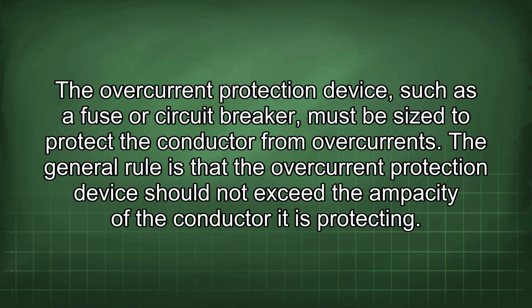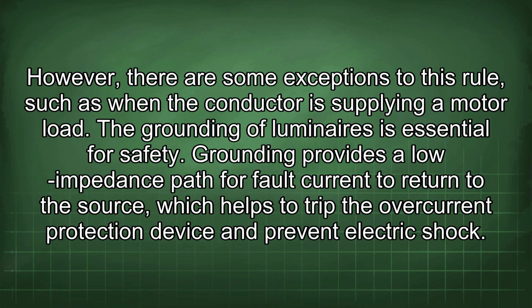The overcurrent protection device, such as a fuse or circuit breaker, must be sized to protect the conductor from overcurrents. The general rule is that the overcurrent protection device should not exceed the ampacity of the conductor it is protecting. However, there are some exceptions to this rule, such as when the conductor is supplying a motor load.